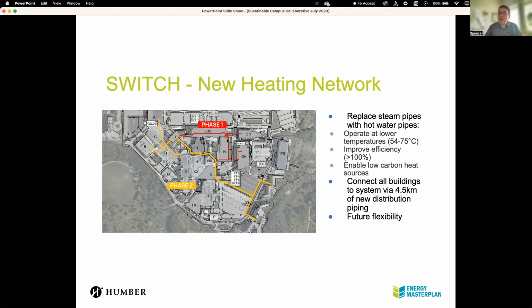Another thing we did here was we were worried about redundancy. So we've built a loop, if you can see around there. It's not a round loop, but there is a loop, and that's all sized with 10-inch pipes that run through the buildings at that point. It's there for redundancy, so if we ever get a break, we can feed from the other direction. But also we have additional capacity, so if somebody decides we're going to put a new building over here, we can tie into that loop and feed it with the decarbonized system. We're no longer getting islanded buildings with who knows what heating them.